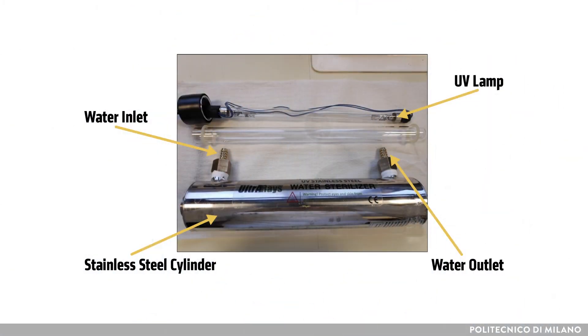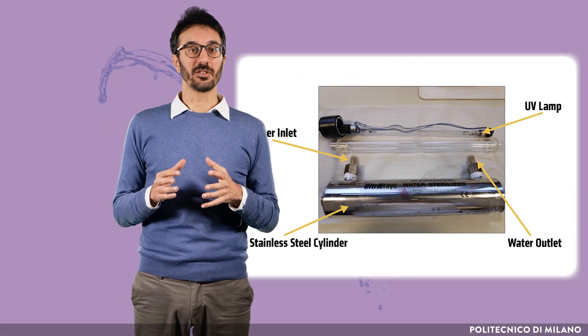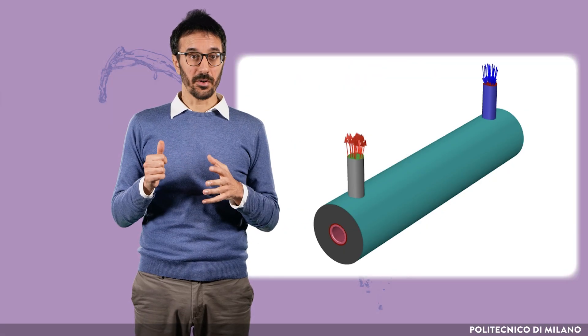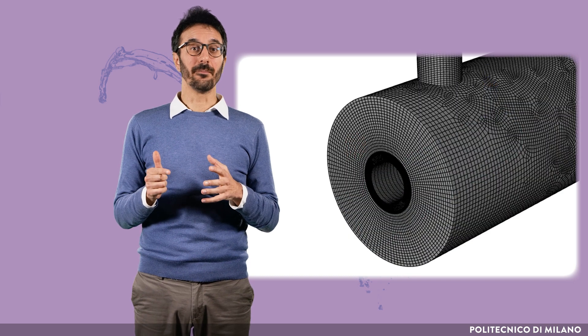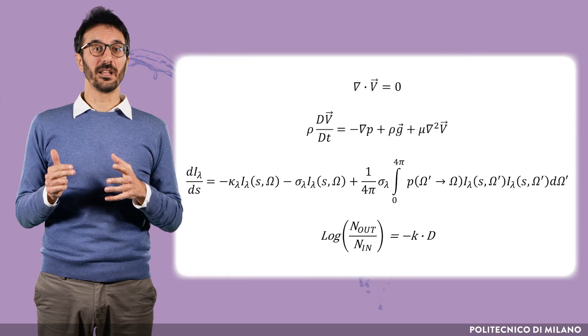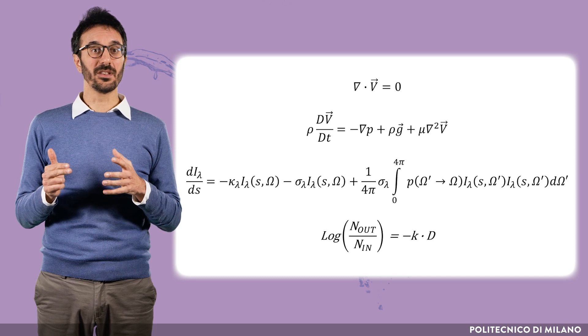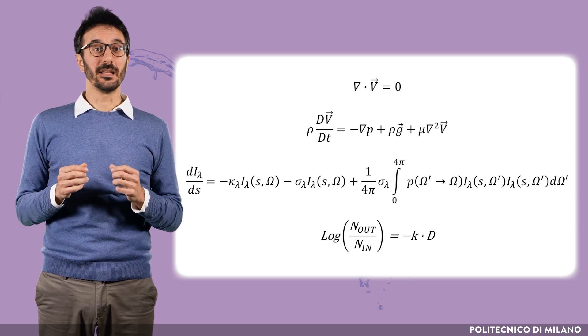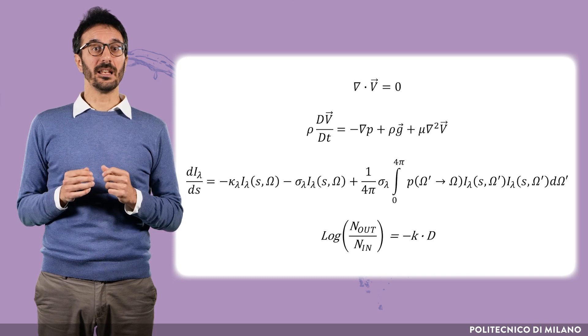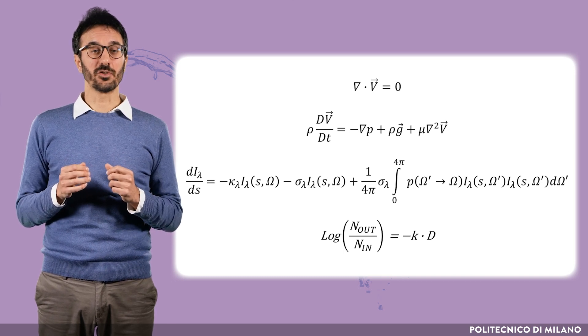Let's model a typical pressurized vessel for UV disinfection. It is a stainless steel cylinder in which water flows from one side to the other. During its passage, the water is irradiated by the UV lamp positioned in the middle, and the pathogens are inactivated. The sequence for modeling such a reactor is: reproduce the geometry in the virtual environment; create the mesh; define and solve the characteristic equations — in this case, the Navier-Stokes equation for fluid dynamics, the radiative transfer equation for UV propagation, and the Chick-Watson equation for pathogen inactivation.